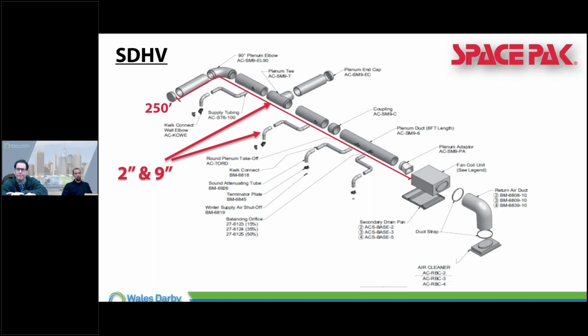So that's total equivalent. We get some elbows in there, like this example, and a T right off the bat. We're at 45 feet - 15 feet for elbows, 30 feet for T's. We take that into consideration. Now we're at 205 feet, a straight run we can possibly run. It's still a ton of duct work that we can get up in an attic.